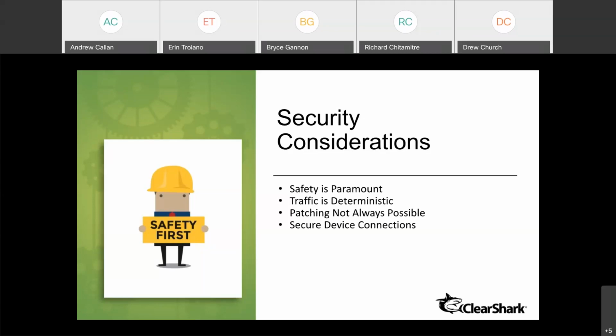Regular scanning for vulnerabilities unleashes a massive amount of traffic onto a network. Something like a Nessus scan that isn't dialed all the way back to 0.5. A huge amount of packets hits every device that they can reach. So this may not be an issue for IT devices, servers, laptops, routers, even IoT devices may be better equipped to handle this. But the level of traffic is not what most OT devices are capable of processing. Regular vulnerability scanning knocks these systems offline, and it can endanger critical infrastructure or, in the very worst case, human lives.